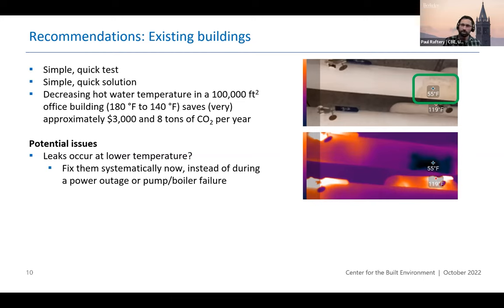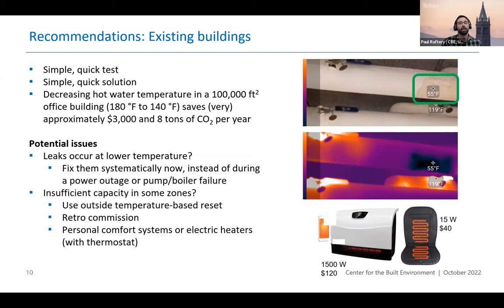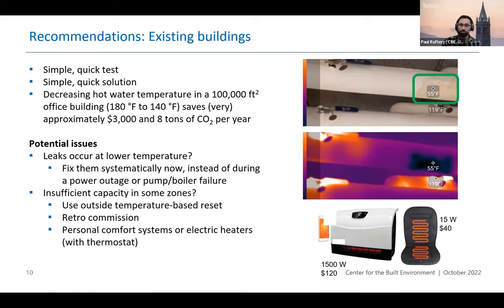We would argue that we should fix those leaks systematically now rather than dealing with leaks throughout your building at the same time as some inevitable power failure or pump or boiler failure. The other issue is that you can have insufficient capacity in a small number of zones when you go to lower supply water temperatures. You can address these for most of the year by implementing supply temperature reset strategies, or retro-commission, as these issues are often due to minor equipment failure at specific zones or incorrect airflow set points. You can even consider installing small supplemental heaters in a small number of zones — the cost of operating those electric heating devices is actually quite small relative to the overall savings within the whole building.